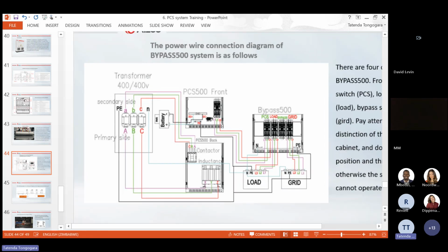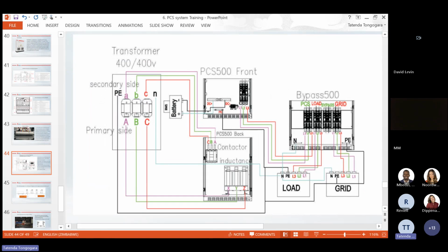So when you're connecting your transformer, please follow the SLD diagrams that I'm going to share with you. This is how you connect your transformer. The secondary side of the transformer is connected to the contactor at the back of the PCS. That is 500 in this case. At the back of the PCS, you connect the contactor to the secondary side of the transformer, and then the primary side, you connect it to the inductance of the PCS. And then the load and grid is just the same. So you find this at the front of your bypass.